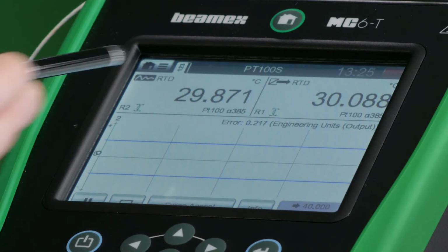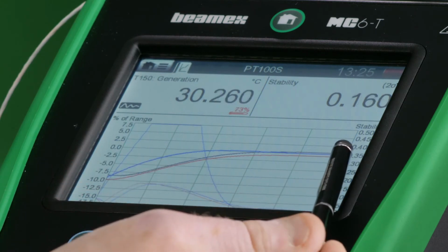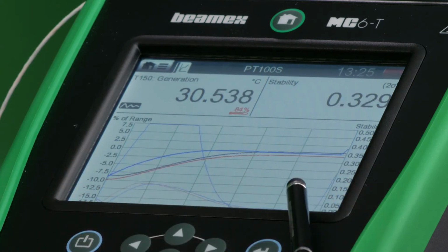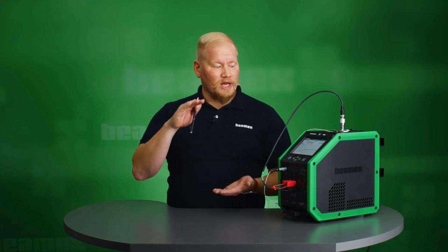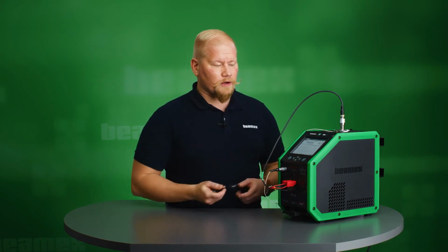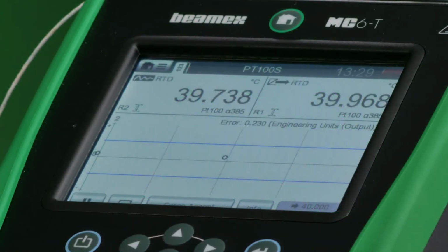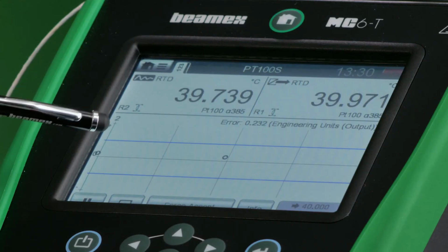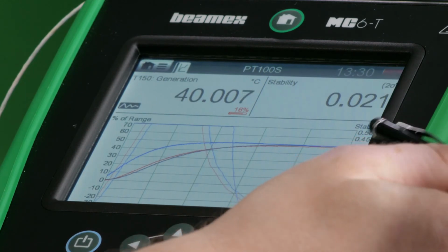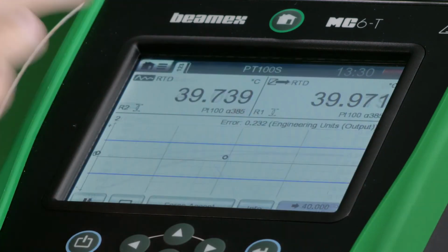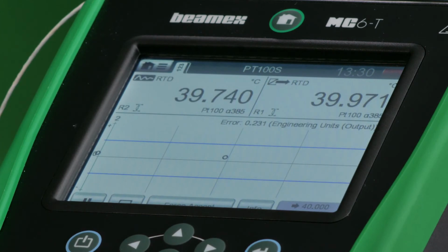It has recorded it. We can see that it started heating, so the temperature graph is going to go up, and also the stability value is going to go up because the temperature is changing. And we are now going for the 40 Celsius set point. Now we're very close to reaching our second set point. In reality, a technician wouldn't need to be following this because it is all automated. They could be preparing for the next job, the next calibration, or whatever they like to do. Now when I look at my second set point, I can check that my stability is getting very close to where it should be. So any second now, it's going to be able to record the second set point.